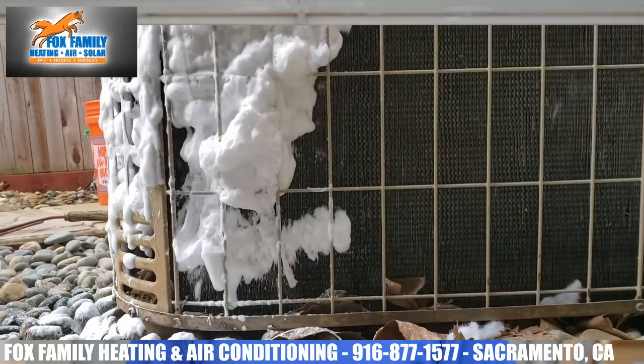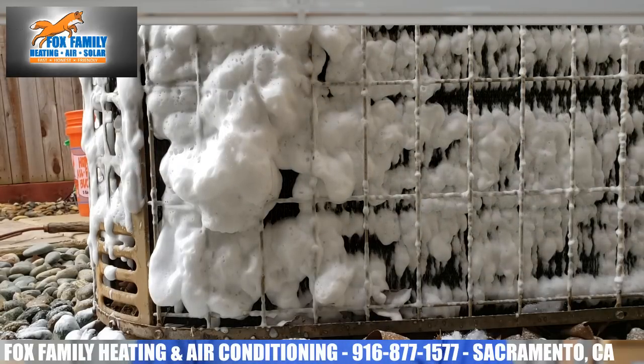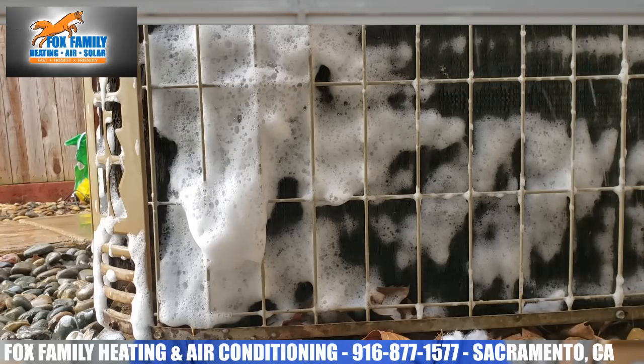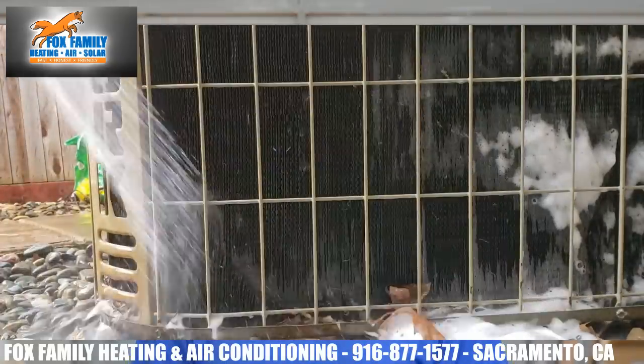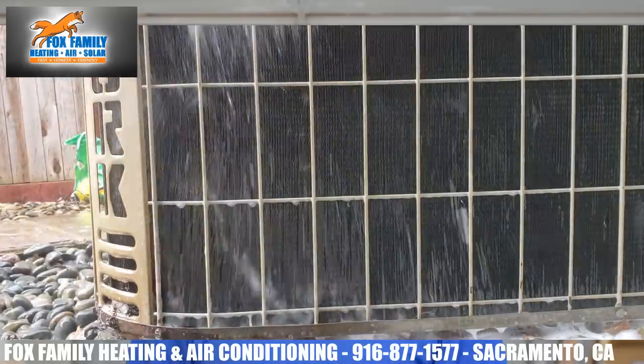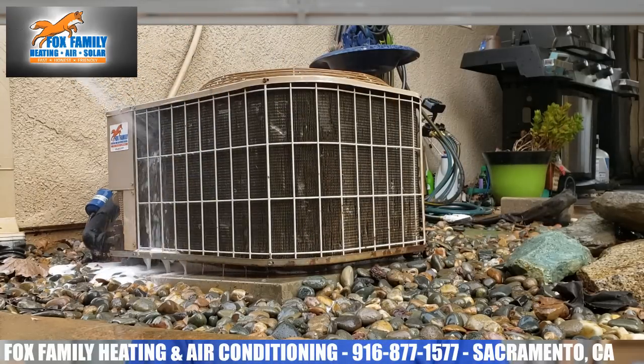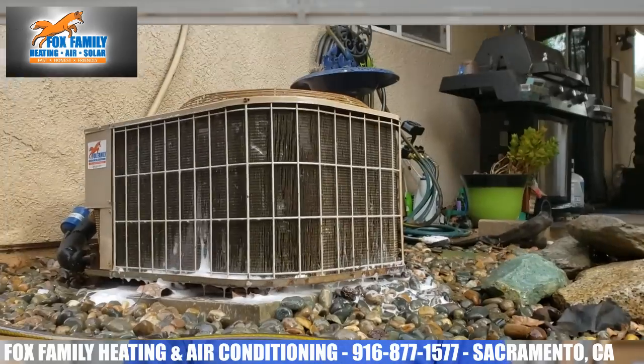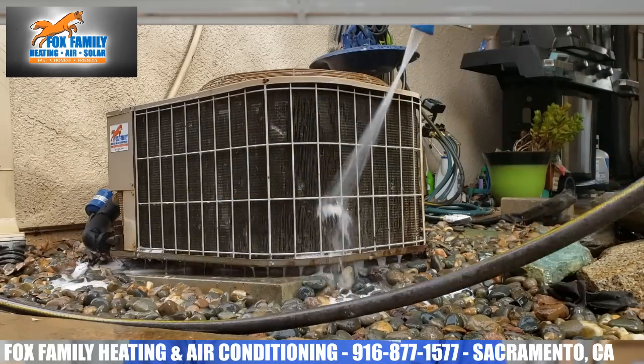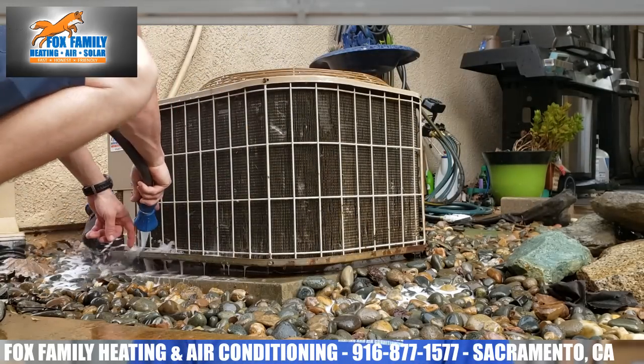Washing the AC outside unit every now and then would be nice too. It doesn't take much energy, and it doesn't require any soapy solutions. But if that coil on the outside AC gets clogged like a dirty filter, high pressures can occur in the refrigerant system, causing loud squealing noises. Please don't use a pressure washer — you'll destroy the parts crucial for airflow and heat transfer. Use just enough pressure from the hose to knock off loose dirt and small debris. Also, try not to bend any of the fins that surround the AC, called the condenser coils, because flattening them will create more noise and airflow problems.